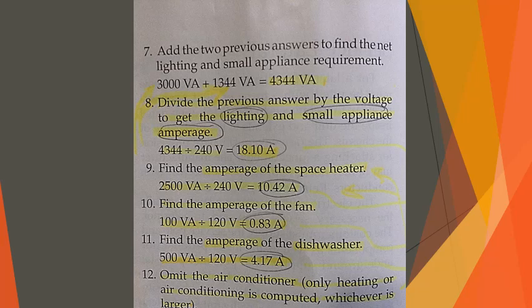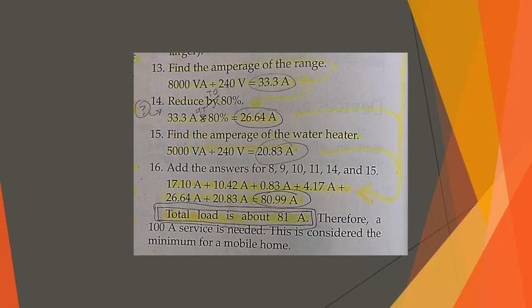And then finally, step 16, add all the answers for steps 8, 9, 10, 11, 14, and 15, which are in this case 18.10 amps plus 10.42 amps plus 0.83 amps plus 4.17 amps plus 26.64 amps plus 20.83 amps, which gives us a total of 80.99 amps. So the total is about 81 amps, therefore a 100 amp service is needed. This is considered the minimum for a mobile home.